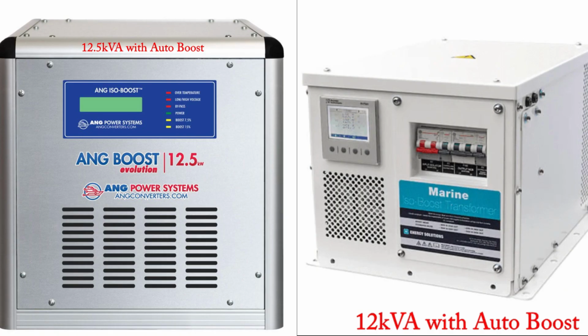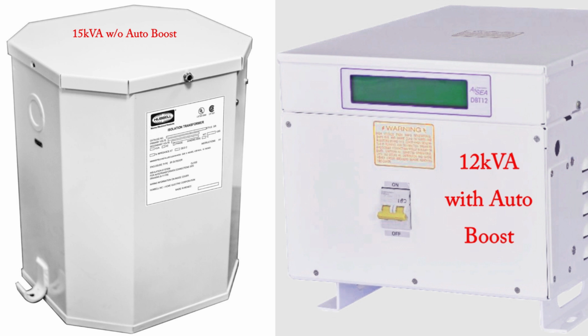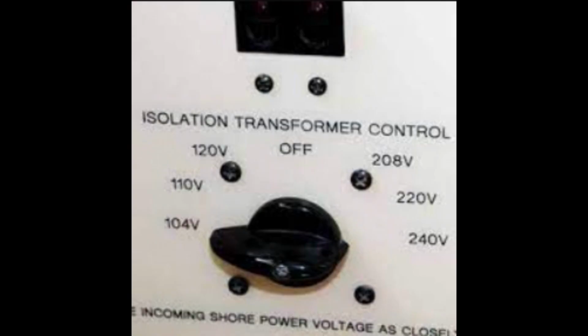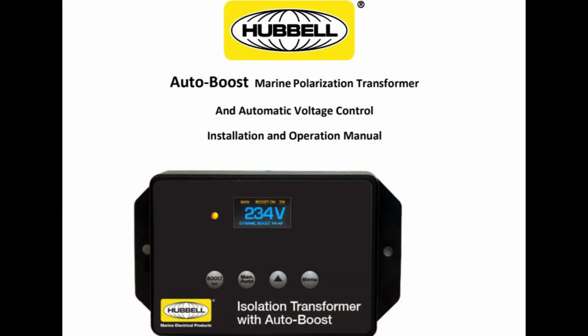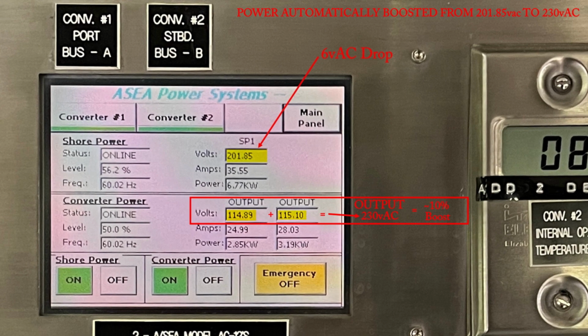One solution for this is to use what's called a buck and boost isolation transformer, which typically has a limited voltage range from about 170 volts to 270 volts. These transformers can either be fixed, have several taps for different voltages, or the more expensive units will automatically adjust to your desired output voltage.